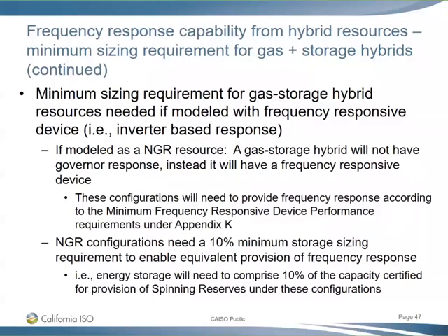What we're really going to propose is that you need to have 10% of the overall certified size of the ancillary service capacity made up by a storage device. So essentially, if you were a 50 megawatt combined hybrid resource modeled as an NGR, you would have to have 5 megawatts of storage behind that to provide the equivalent amount of frequency response you could if you were just a traditional thermal generator. The intent behind this concept is to provide equivalent frequency responsive capability and responsiveness between any of these different hybrid resources.